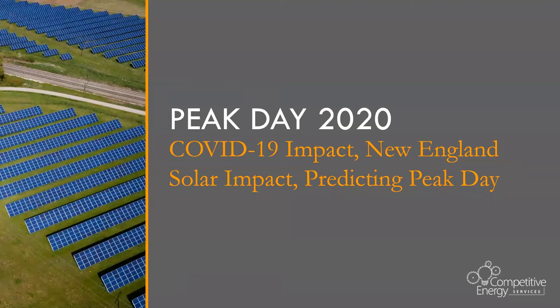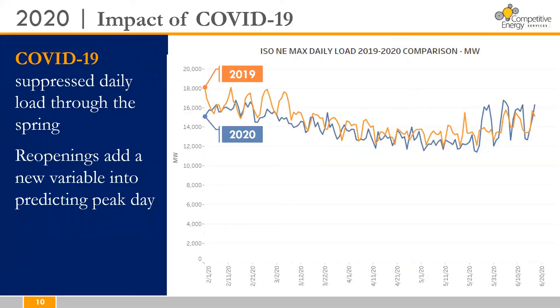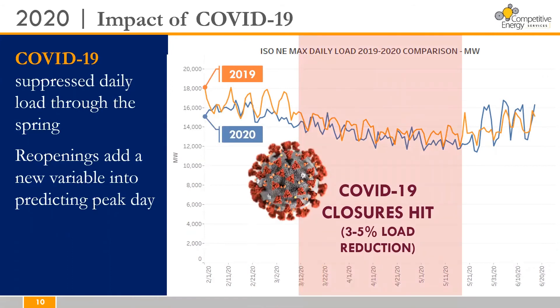So what can we expect for summer 2020? First, let's look at how COVID-19 has impacted daily electricity load here in New England. This graph shows the maximum daily load — the system's peak demand for each day in 2019 compared to 2020, between February and late June. 2019 is shown by the orange line, while 2020 is shown in blue. Overall, peak demand load on the New England grid has been between three and five percent lower between March and May due to COVID-19. Residential loads have been higher, while commercial and industrial loads have been lightened due to work-from-home requirements and business slowdowns. But as lockdowns have eased heading into June and the cooling load has begun to intensify, demand trends appear to be returning to near or above 2019 levels.